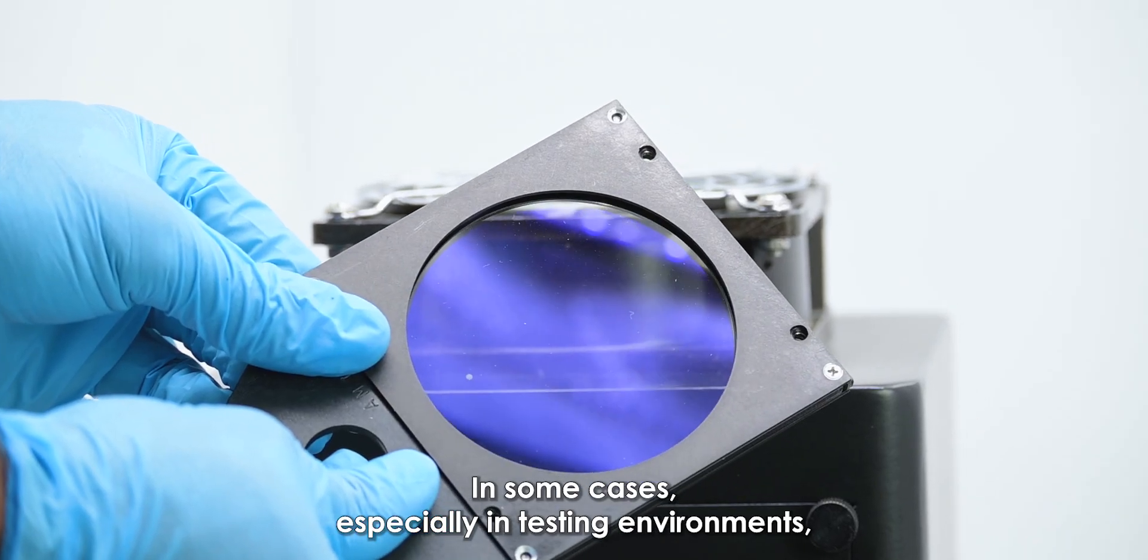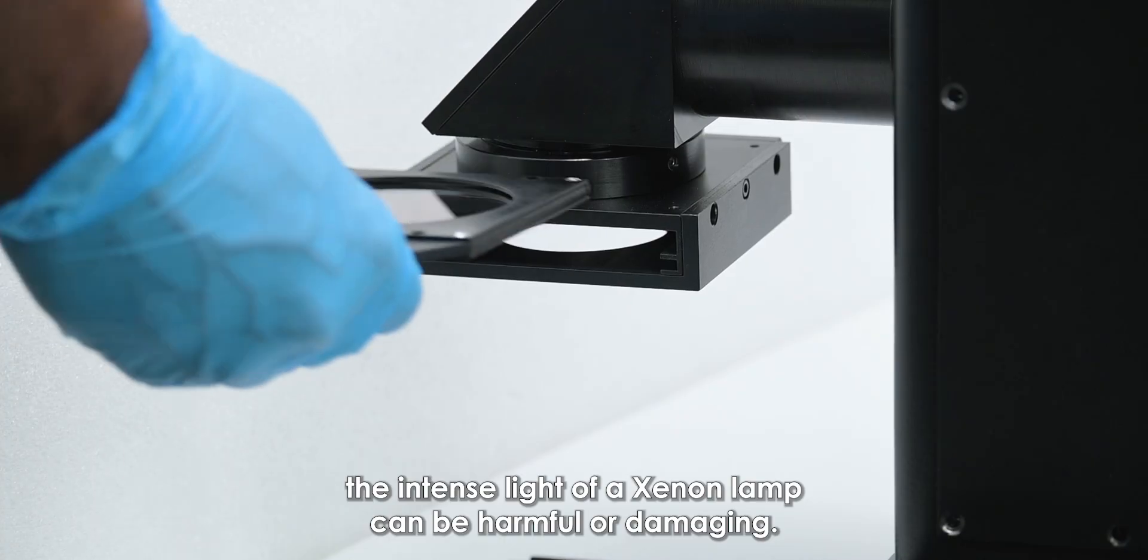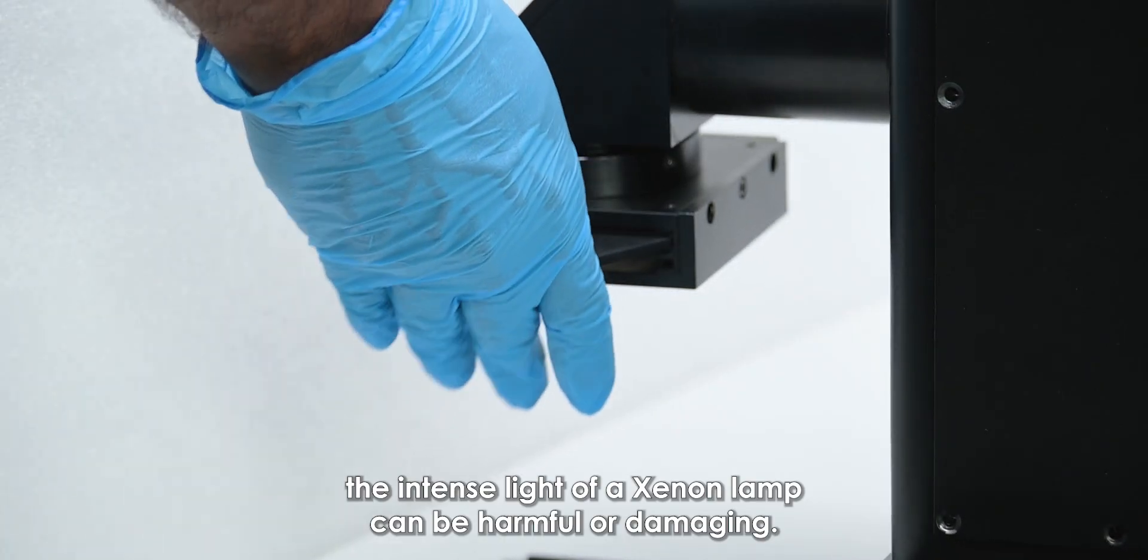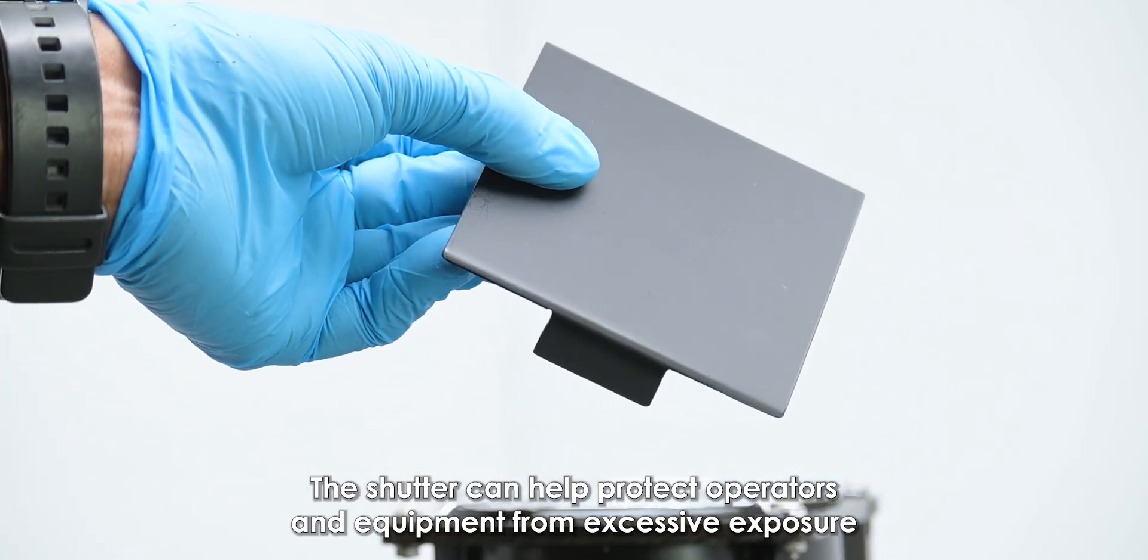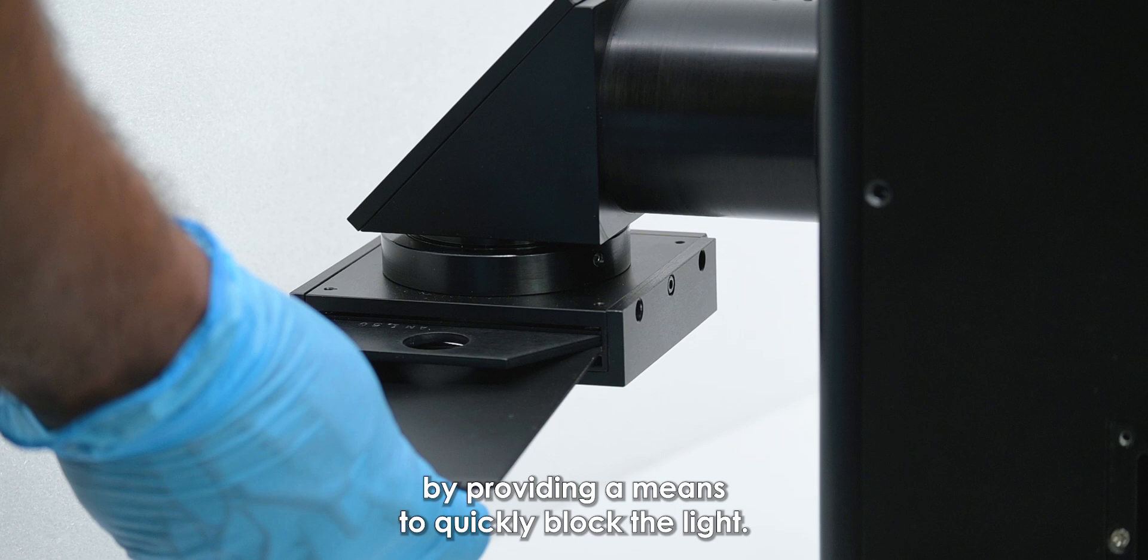In some cases, especially in testing environments, the intense light of a xenon lamp can be harmful or damaging. The shutter can help protect operators and equipment from excessive exposure by providing a means to quickly block the light.